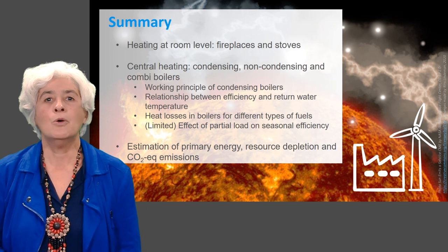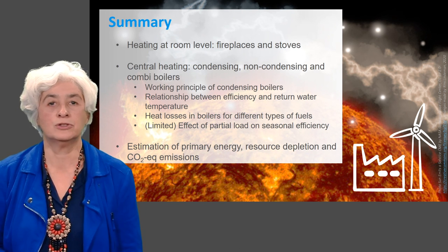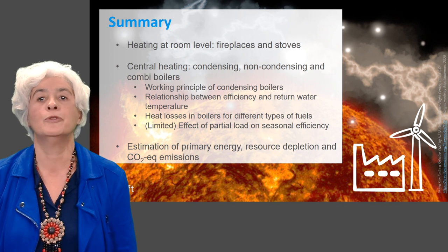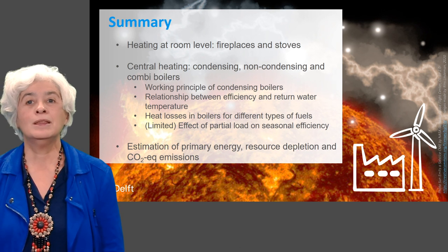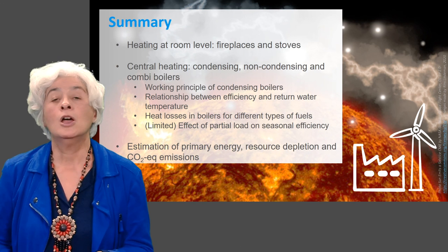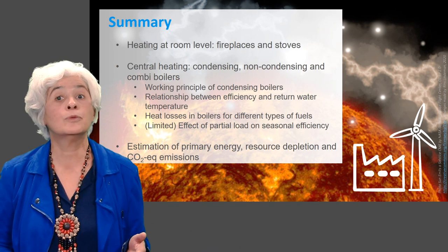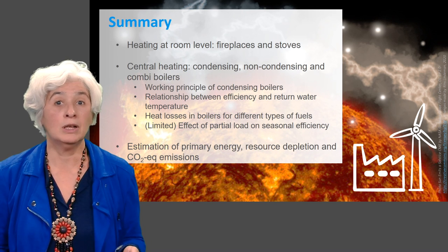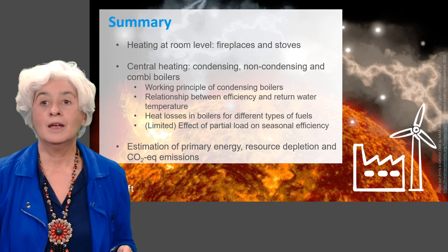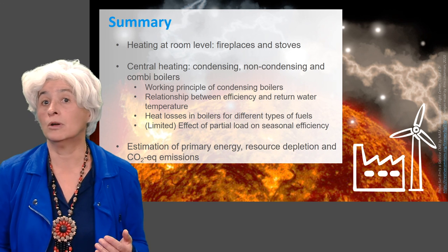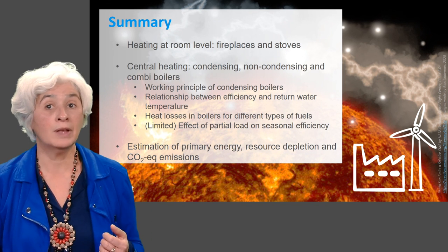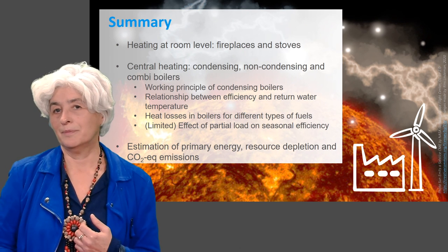In this lecture, you have learned how heat production by fuel combustion works. We handled systems working at room level like fireplaces and stoves, then central heating boilers and their connection to radiators or air handling units. We covered the principle of condensing boilers and the relationship between their efficiency and return water temperature, different heat losses in a boiler, the influence of partial load on seasonal efficiency, and efficiency ranges for different fuels and boiler types. Finally, we found that a non-condensing boiler of efficiency 0.7 emits 57% less CO2 than an electrical boiler powered by the Dutch electricity grid. Thank you for your attention.